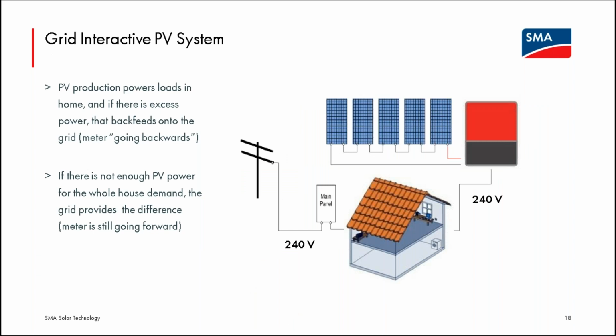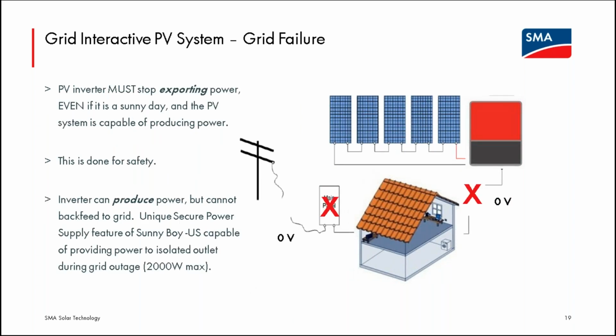So a grid-tied PV system without any type of Sunny Island works very, very well. But as soon as the grid goes away, the inverter says, okay, it's not safe for me to export power, even to the home that it's attached to. So there aren't many options for allowing a grid-tied inverter to provide power without a battery backup system. SMA Secure Power Supply is one of the very few that can even do that.